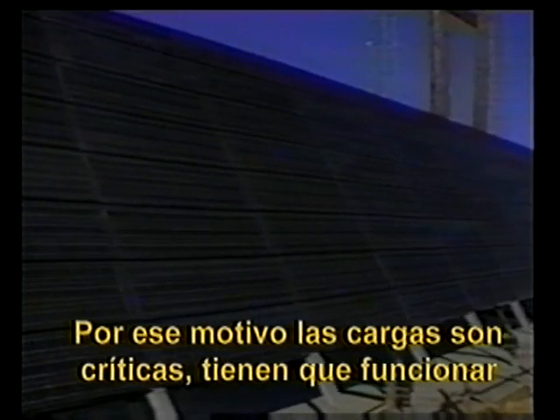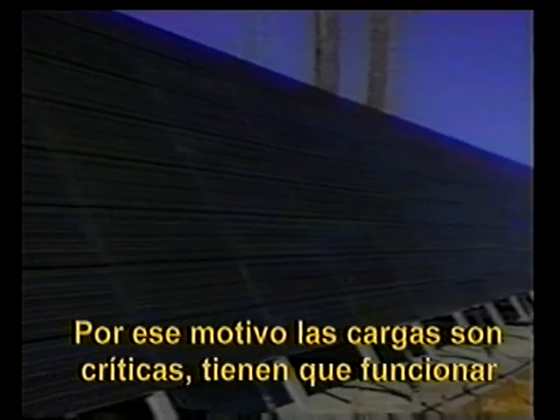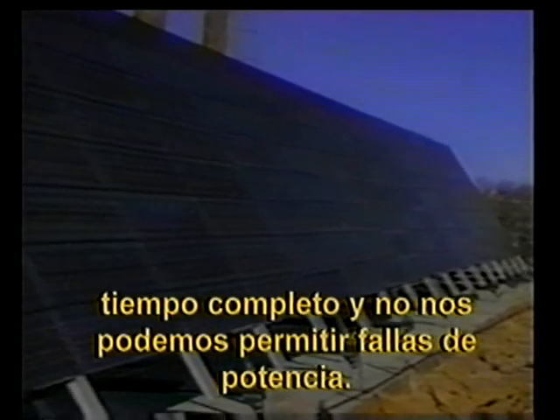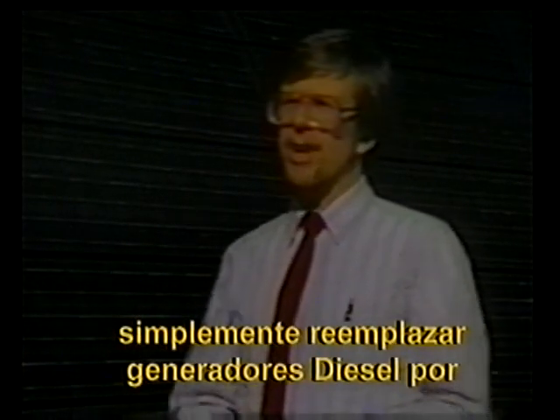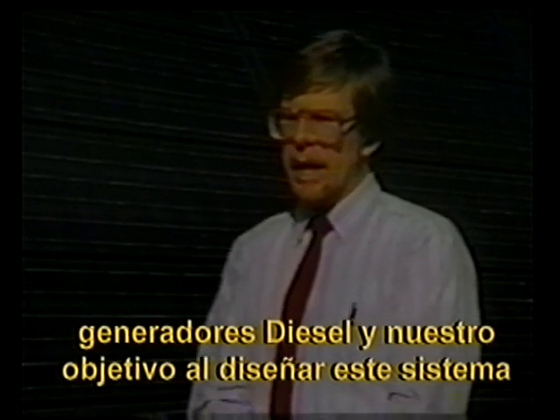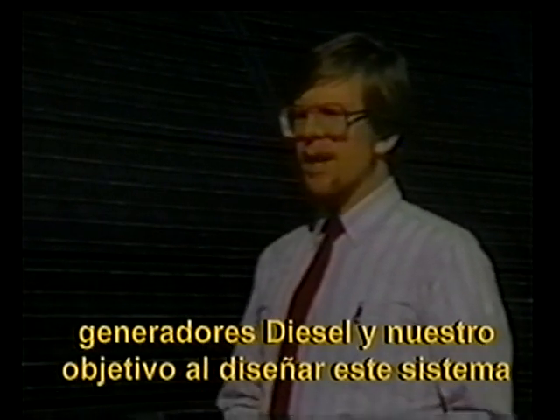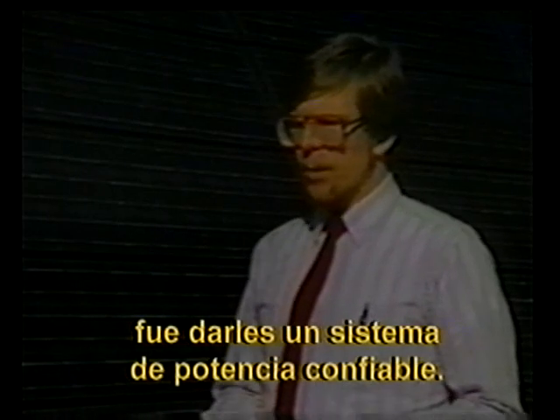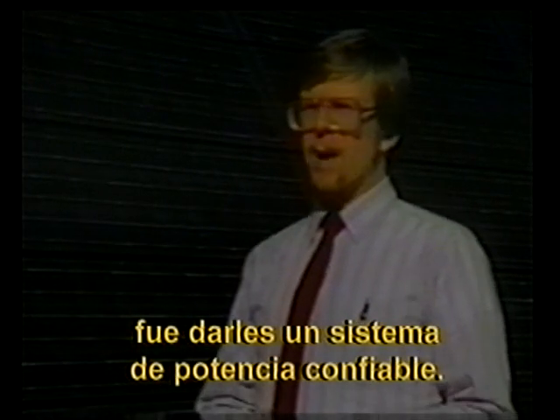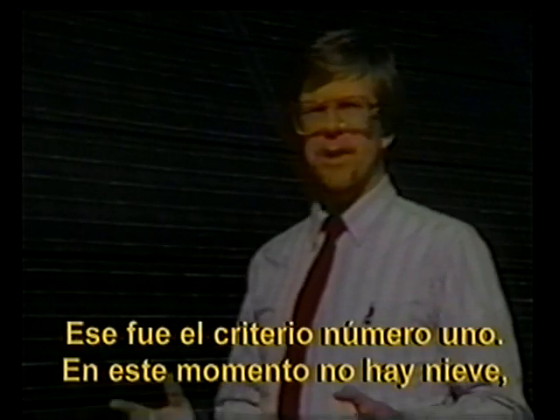And because of that, it's critical. The loads are critical that they operate full-time. There cannot be a power failure. This was state-of-the-art. They wanted to go something more than just replacing diesel generators with diesel generators. And our objective in designing this system was to provide them with a reliable power system. That was the #1 criteria.